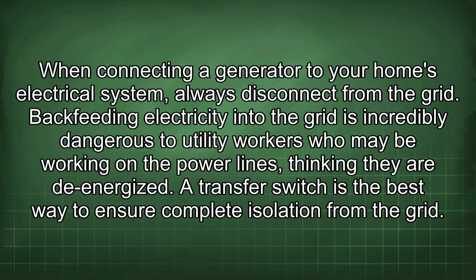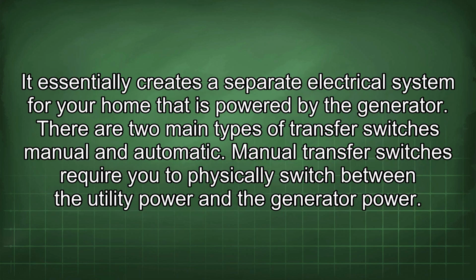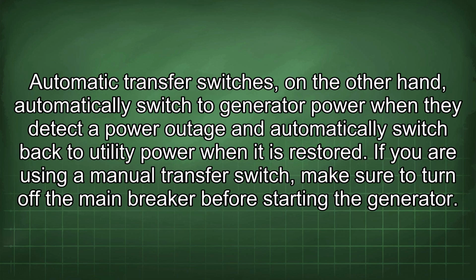Backfeeding electricity into the grid is incredibly dangerous to utility workers who may be working on the power lines thinking they are de-energized. A transfer switch is the best way to ensure complete isolation from the grid. It essentially creates a separate electrical system for your home that is powered by the generator. There are two main types of transfer switches: manual and automatic. Manual transfer switches require you to physically switch between the utility power and the generator power. Automatic transfer switches, on the other hand, automatically switch to generator power when they detect a power outage and automatically switch back to utility power when it is restored.